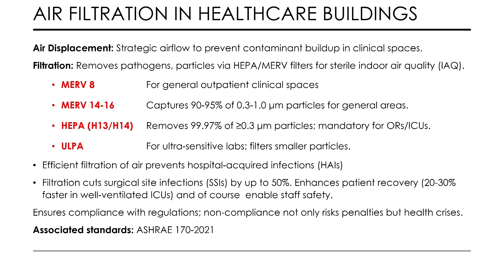So, how does this happen? We are not trying to take the microorganism as such. Microorganisms don't travel on their own. They sit on a particle, and that's why we have to calculate along with that, and that's why we have classified air conditioning with a 0.5 micron. All classifications of clean air are at 0.5. Though microorganisms are smaller than 0.5 microns, they cannot travel on their own. They have to sit on a particle to travel. That's why the filtration classifications of class 100, class 10,000, class 100,000 are based on that.